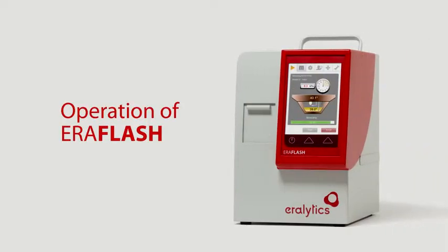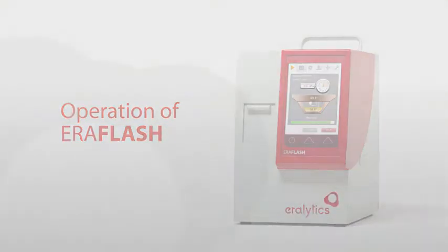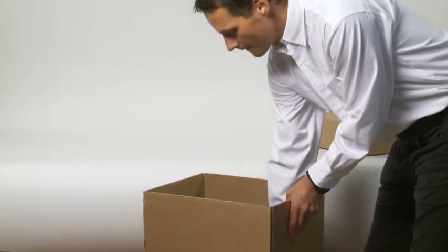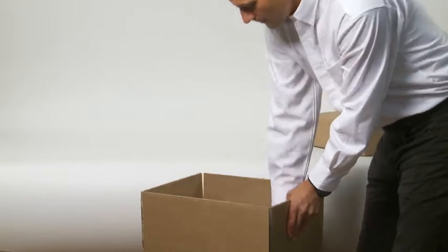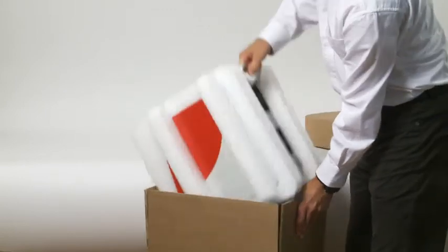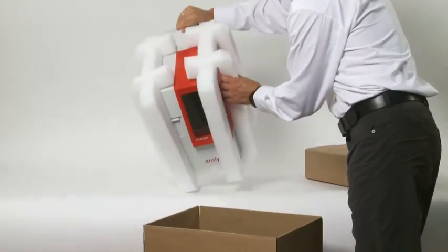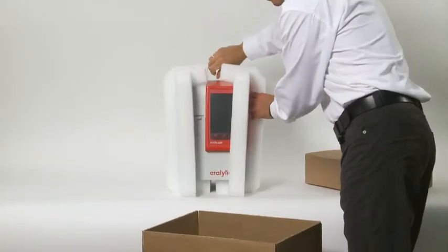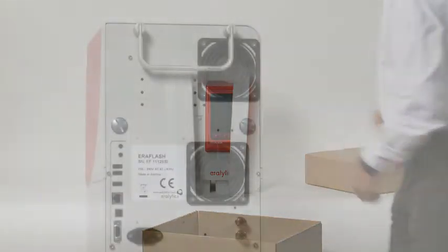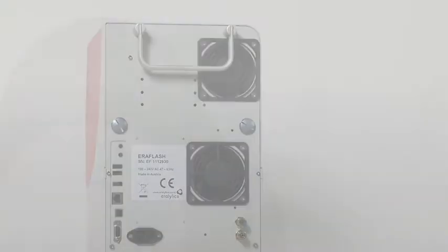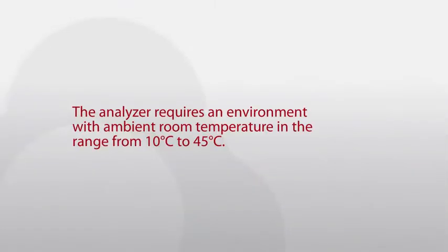Operation of Eralytics Flash Set-Up: After unpacking, place the instrument on a stable benchtop. Make sure that the vent holes of the analyzer are not obstructed. The analyzer requires an environment with ambient room temperature in the range from 10 to 45 degrees Celsius.